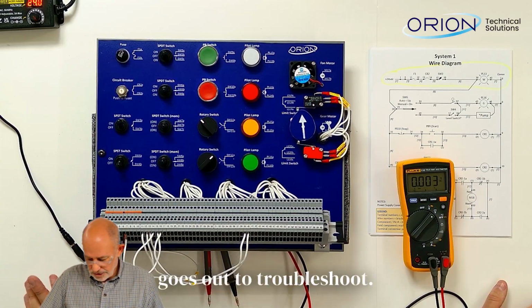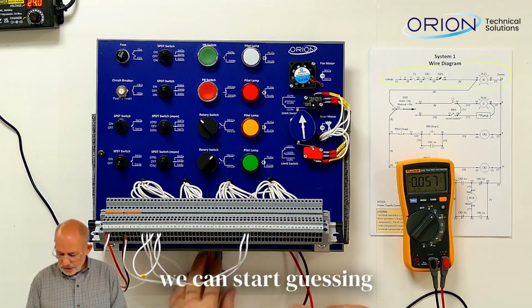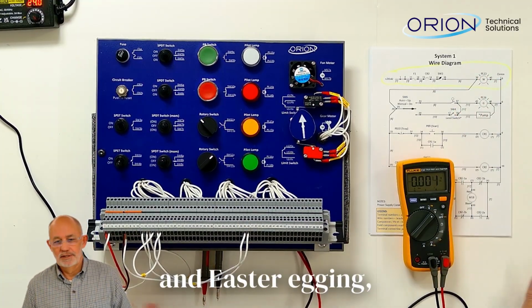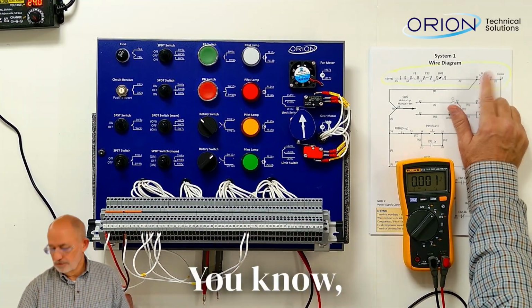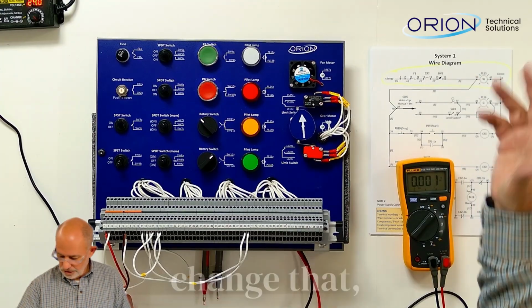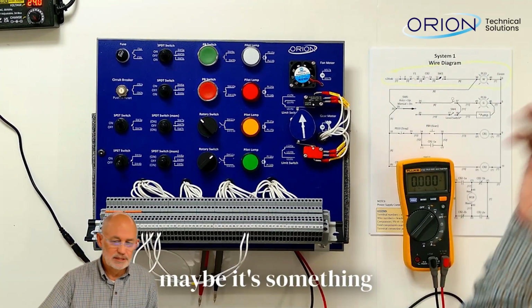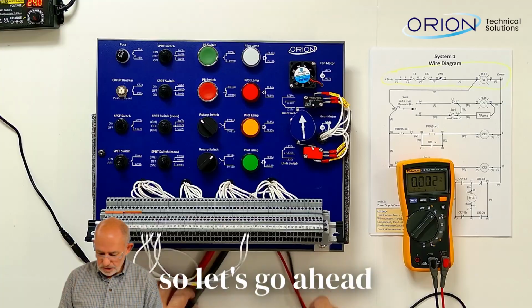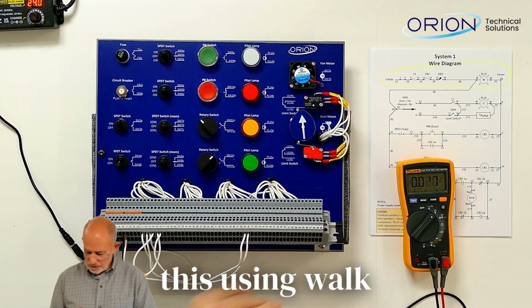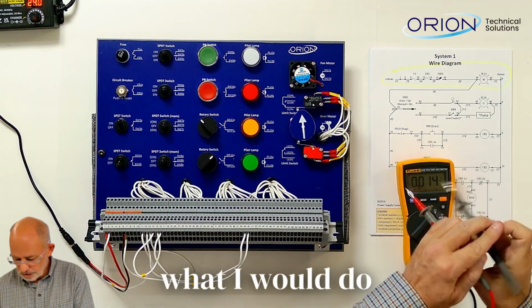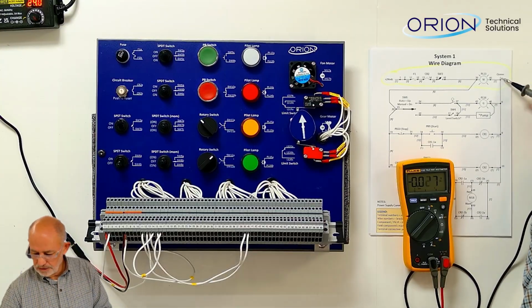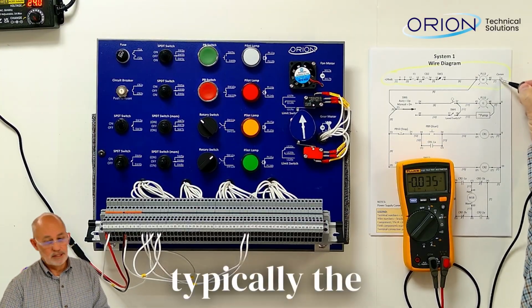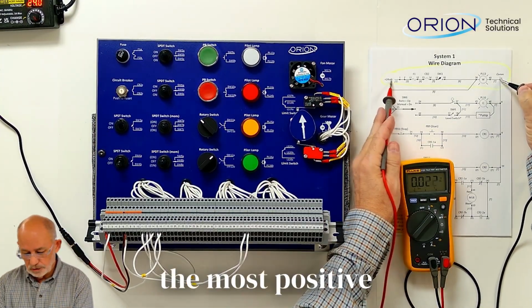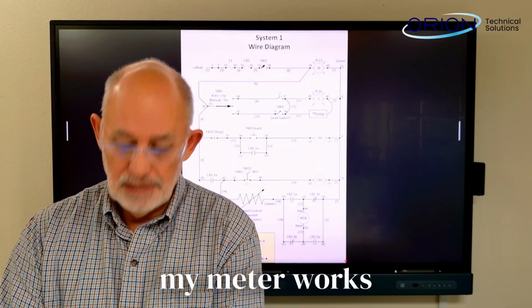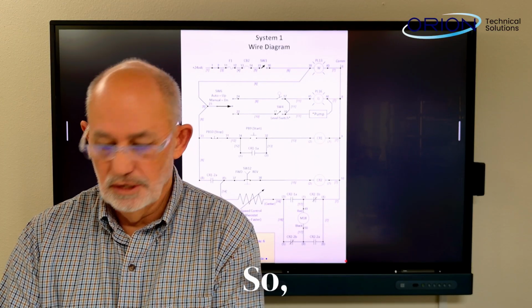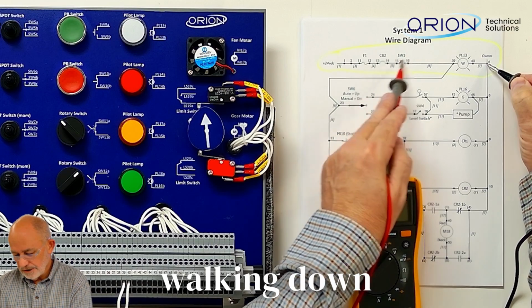And so a technician goes out and troubleshoots. Well, we can start guessing and part swapping and Easter egging, as I like to call it. Swap the white light, change this, change that. But who knows? Maybe it's the switch. Maybe it's something else. So let's go ahead and troubleshoot this using walk the dog. So with walk the dog, what I would do is put the negative lead on typically the most negative point, and then I go to the most positive point to verify my meter works and I do have voltage. So then I will start walking down the line.